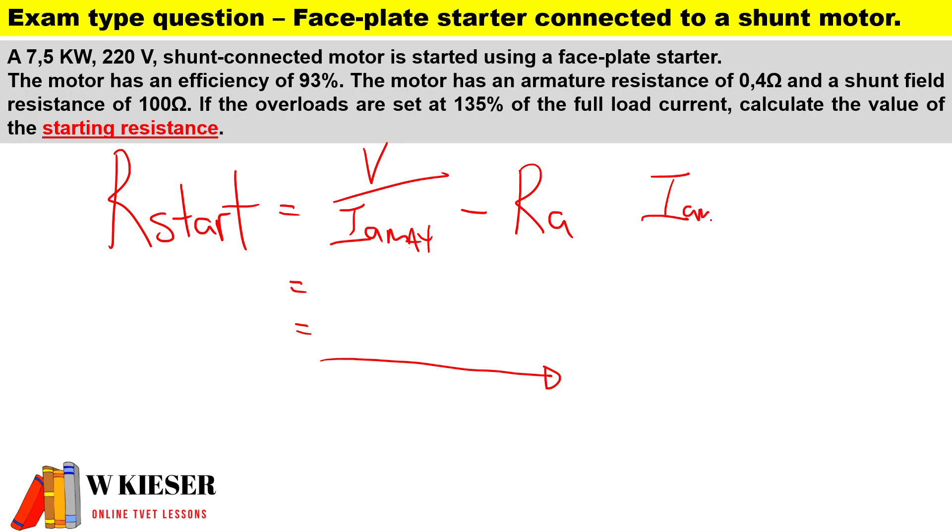Just to show you how we'll calculate I_a_max ahead of time: To calculate the maximum armature current, I will take the overload which is set at 135%, divide that by 100, and then multiply it by I_a. That will give us I_a_max.